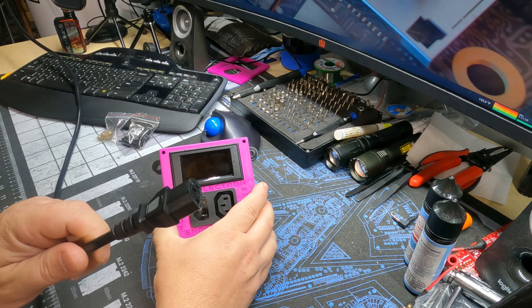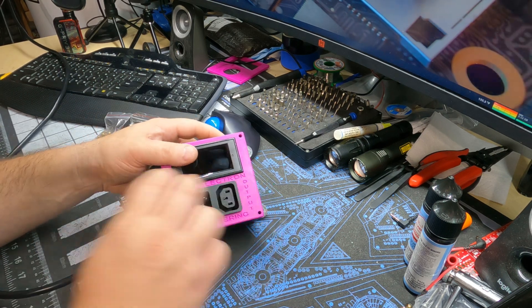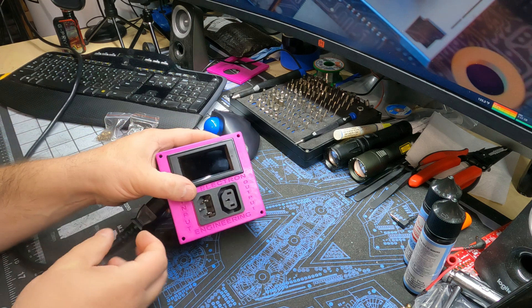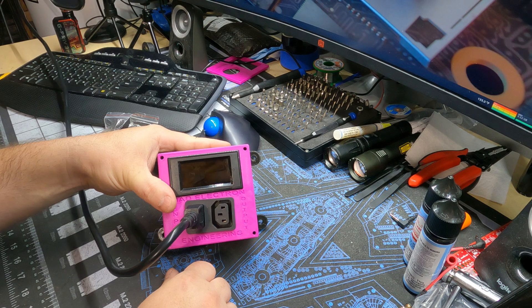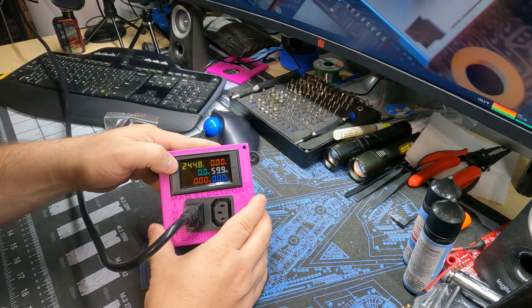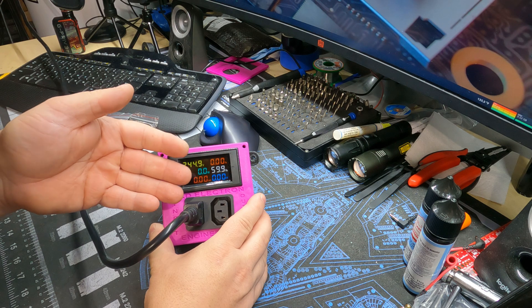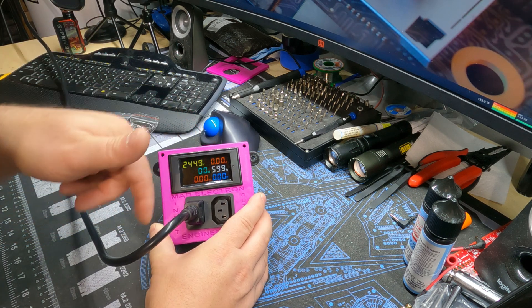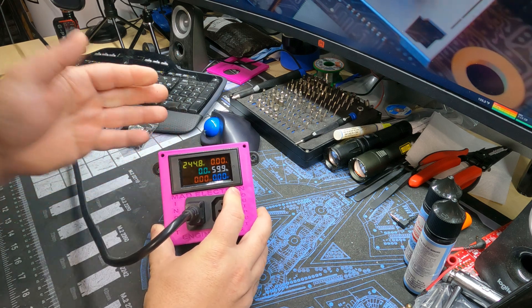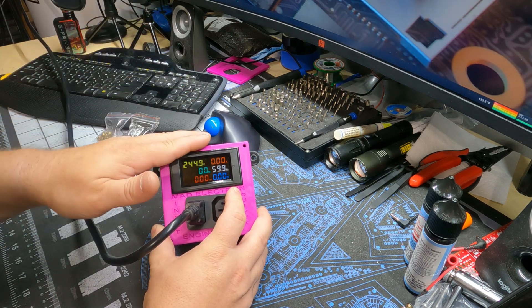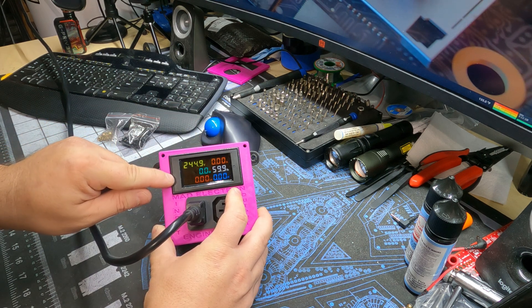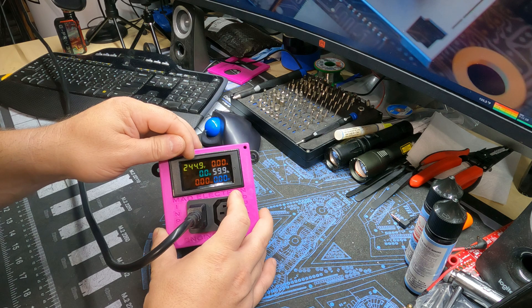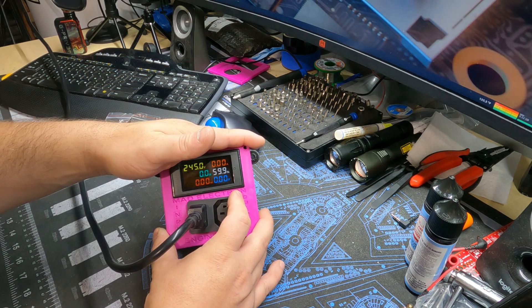Let's unplug this. I have to hold this down since it's not glued in yet. Now this is coming from my 240-volt PDU. Again, you use the input. There you go—244.9 volts. So this works as long as it's wired up in this direction. You can do 120 or 240 with this meter. The meter can handle input voltage up to 250, so we're within five volts of the max, but it handles it perfectly fine.